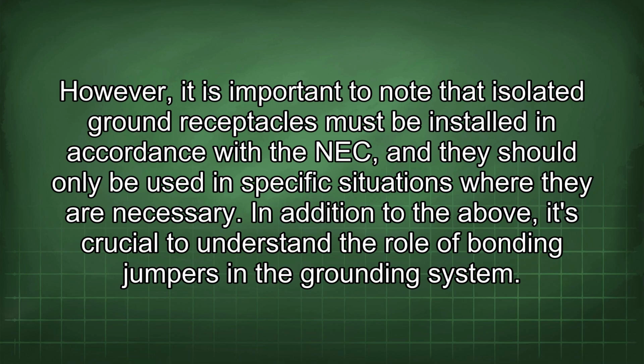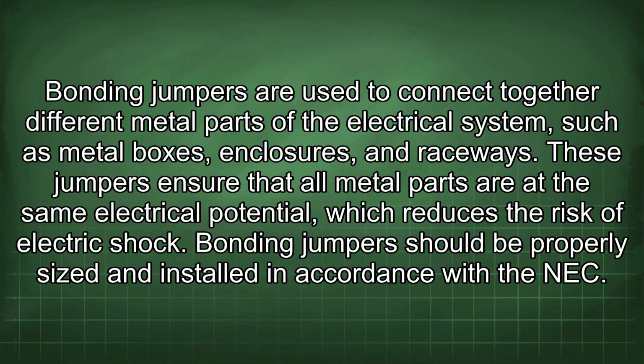In addition to the above, it's crucial to understand the role of bonding jumpers in the grounding system. Bonding jumpers are used to connect together different metal parts of the electrical system, such as metal boxes, enclosures, and raceways. These jumpers ensure that all metal parts are at the same electrical potential, which reduces the risk of electric shock. Bonding jumpers should be properly sized and installed in accordance with the NEC.